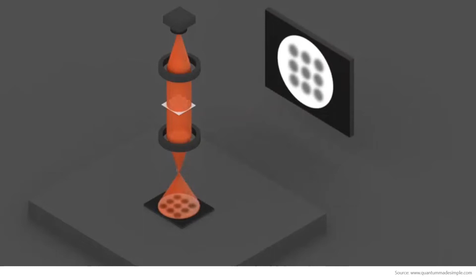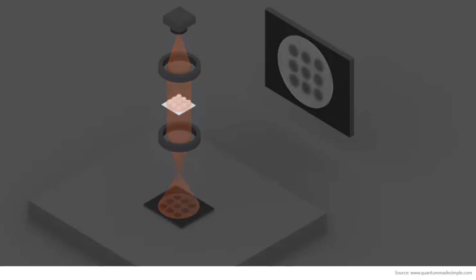The idea of transmission electron microscopy is to use a beam of electrons instead of light. This technique is based on the wave-particle duality of the electrons, and the microscope consists of an emission source, electromagnetic lenses, and a detector. As I said, it is very useful for thin samples, and the electron beam is accelerated and focused by the lenses, such that the beam transmits through the sample, resulting in an image on a detector that is usually fluorescence. The image is of a very high resolution, down to the atomic scale.